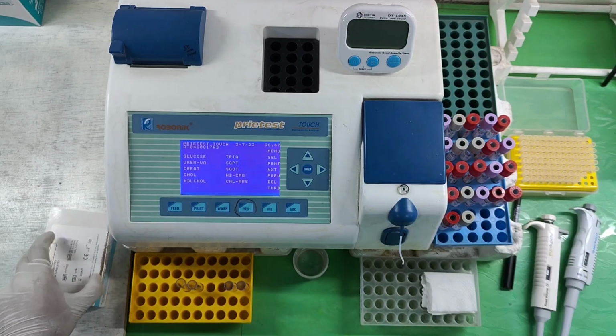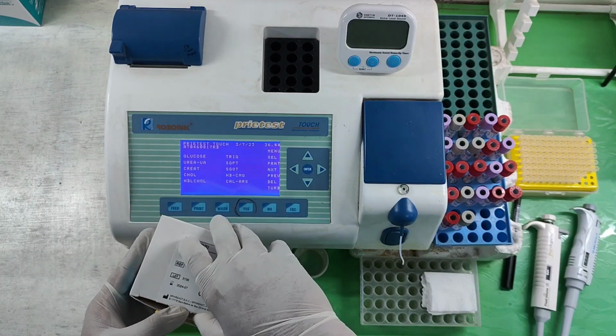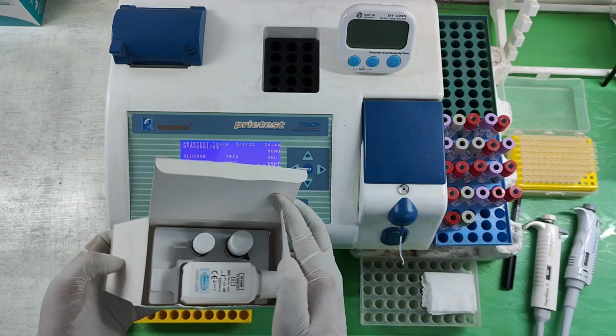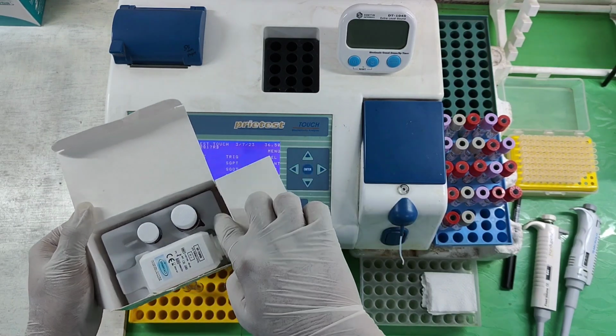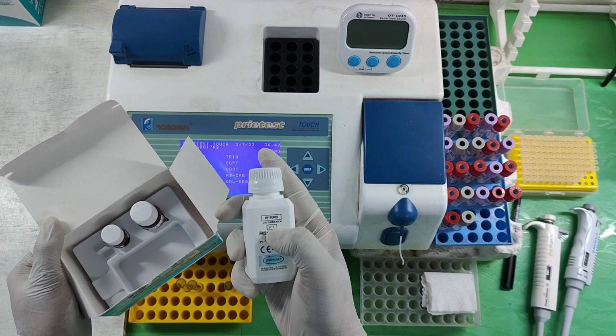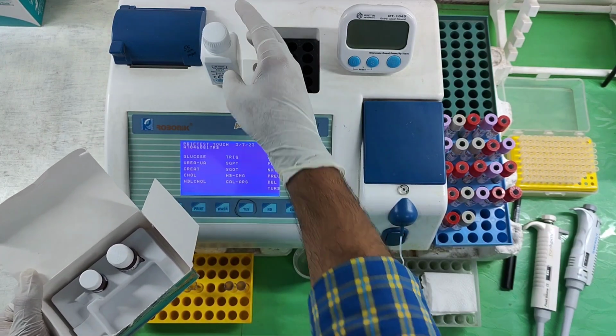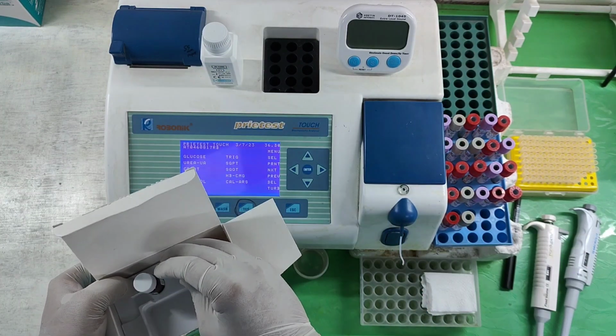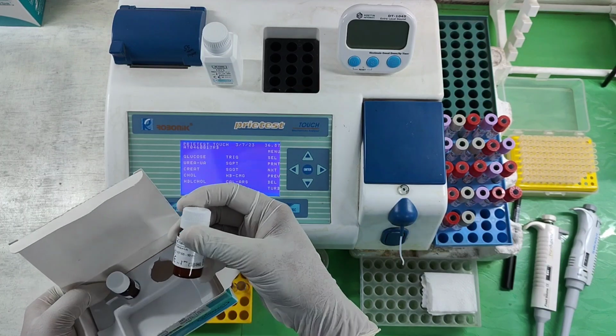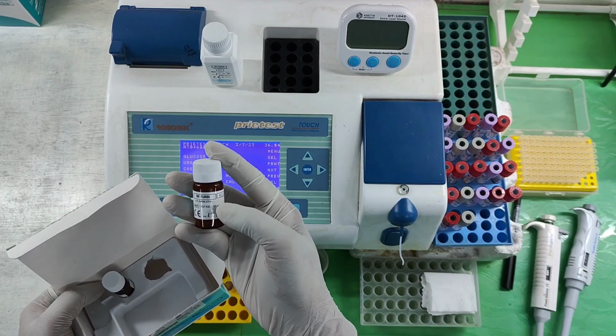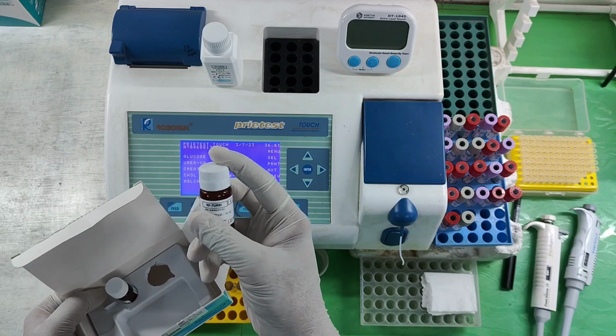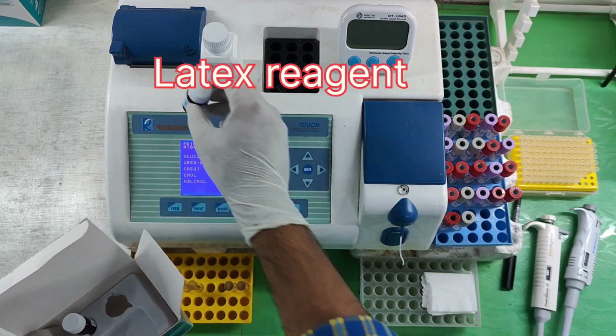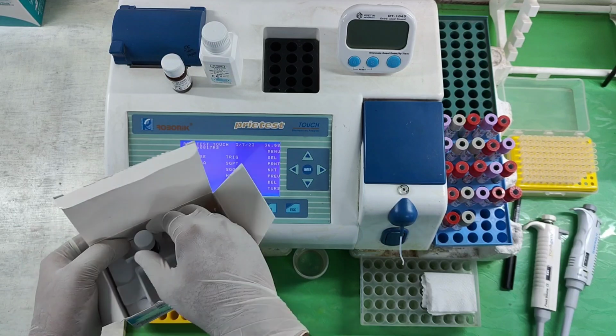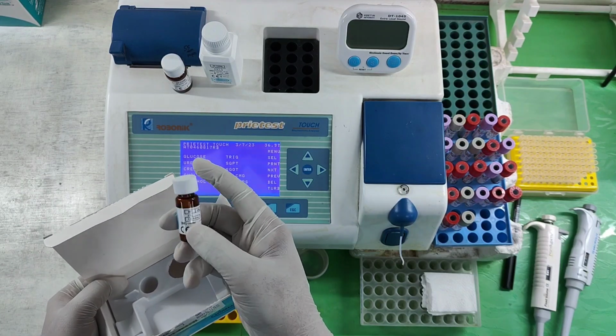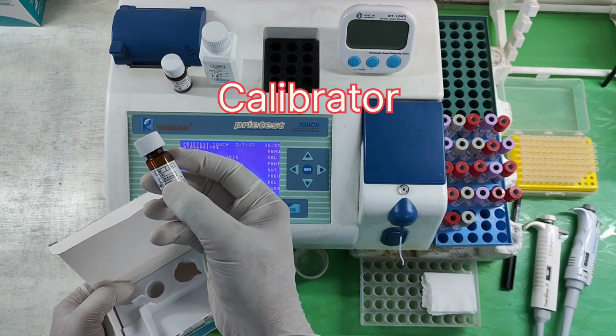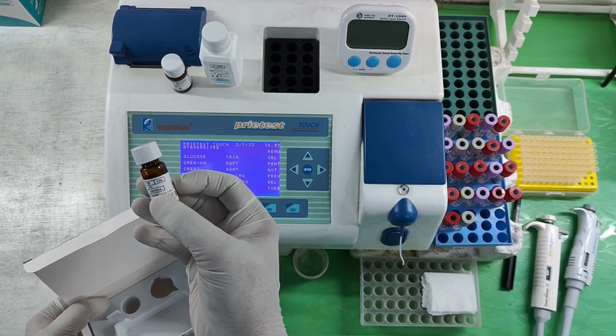First of all, I have to open the kit. You can see here reagent 1, R1, and the reagent 2, RF Turbi Latex. This is the latex reagent, and this is the calibrator. Here is the known value, 139 international unit per ml.